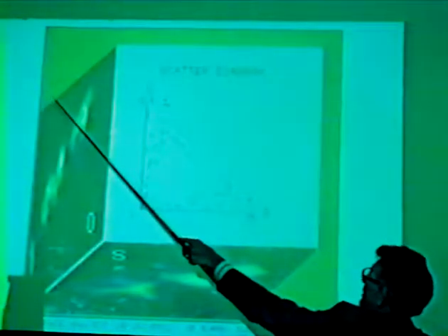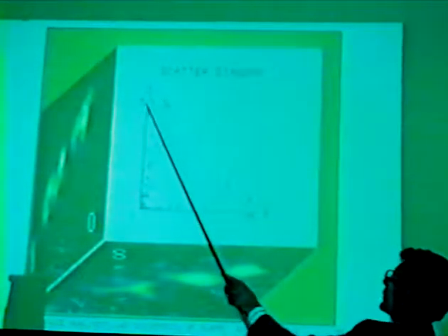He put this together to show what we use to look for correlations between elements on the surface. We've now got this surface sensitivity, and we very often want to look for correlations between elements to see if there are surface compounds or to see if elements are correlated with particular sites on the surface. And what we do is, here for example illustrated by a map for oxygen and a map for sulfur on the surface, is to plot for every single pixel, we would plot the oxygen content, the oxygen signal and the sulfur signal, and that's the thing building up.